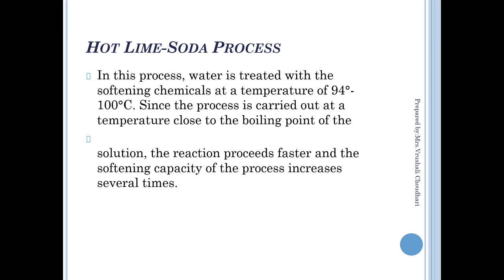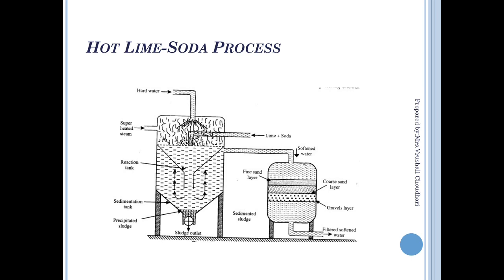To increase the speed of the lime-soda process, the reaction is carried out at a higher temperature — the chemicals are heated above 94 to 100°C — to increase the rate of reaction, make it faster, and increase water softening capacity. Hot water is passed through the tank along with lime and soda. Due to the high temperature, the reaction is faster and the hot water converts soluble calcium and magnesium salts into insoluble precipitates, which settle at the bottom and are removed by the sludge outlet.